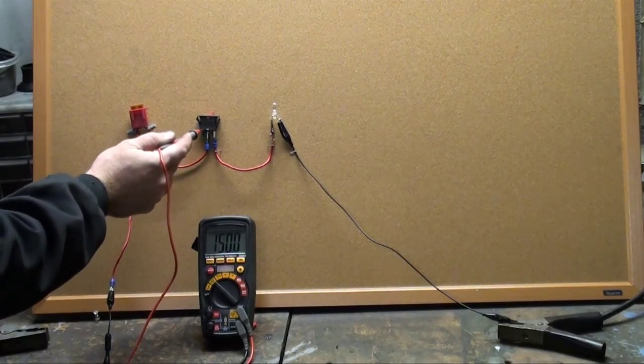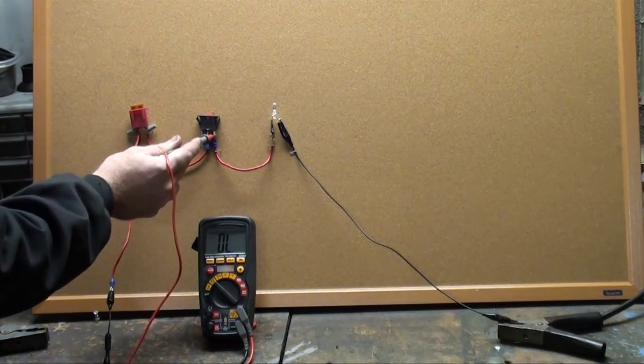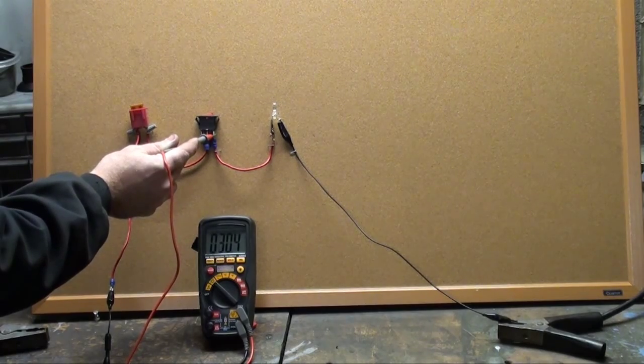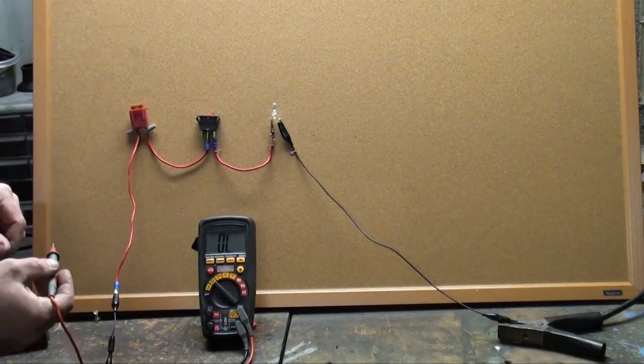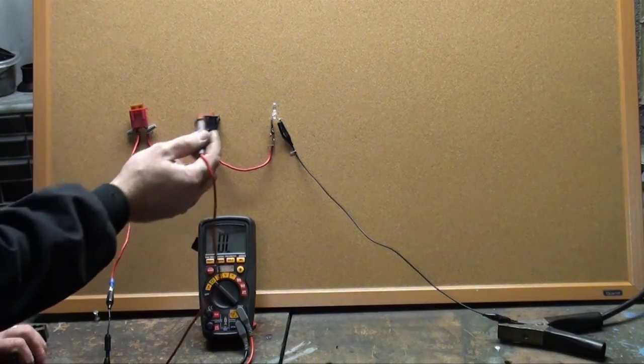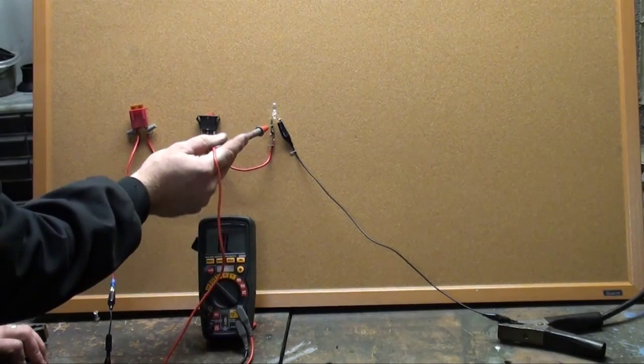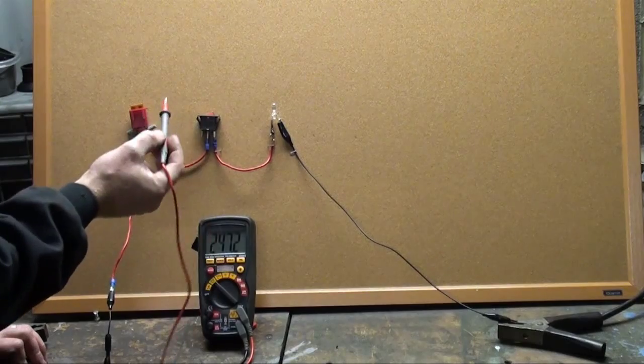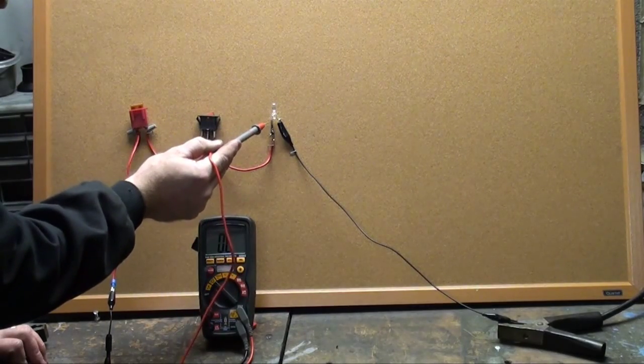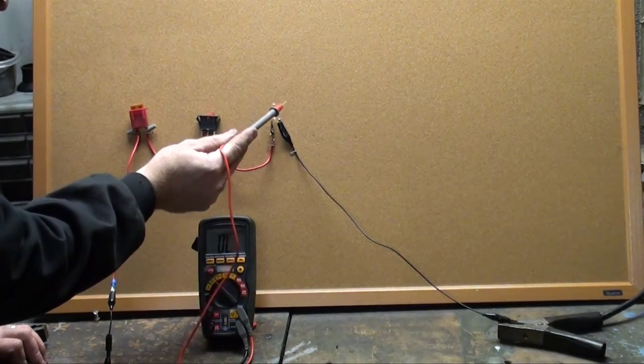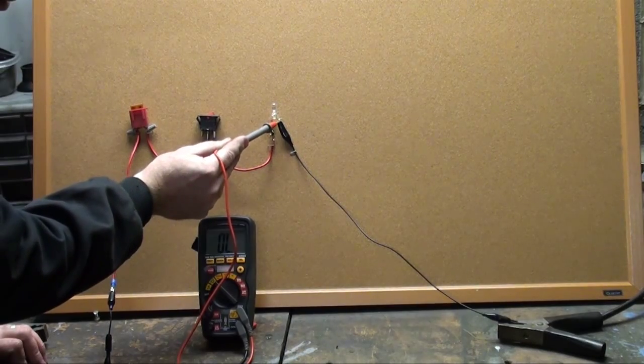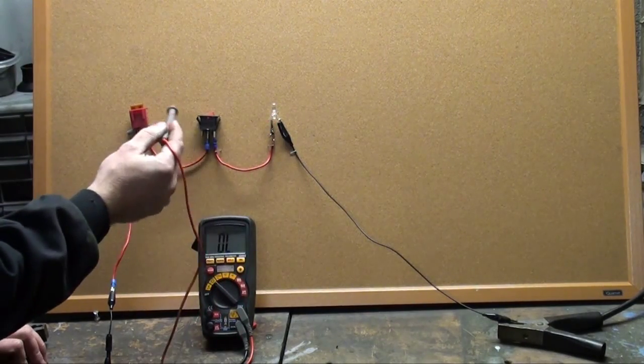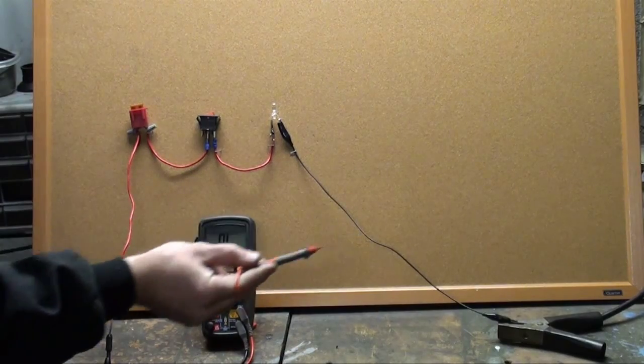So now I have continuity, the circuit is complete on the opposite side of the switch, on the other contact, so we know the contacts in that switch are good. Now we can continue over. Our circuit's complete to the bulb. So let's make sure the filament in that bulb is good, so I should have continuity on this side. And I do. So we know everything in the circuit is complete to ground.